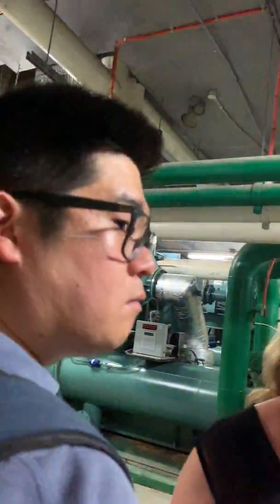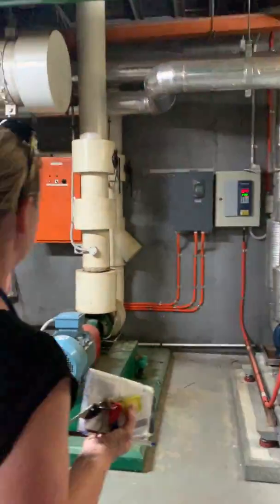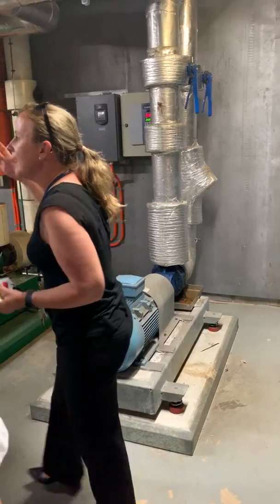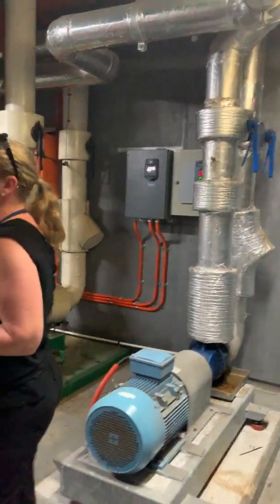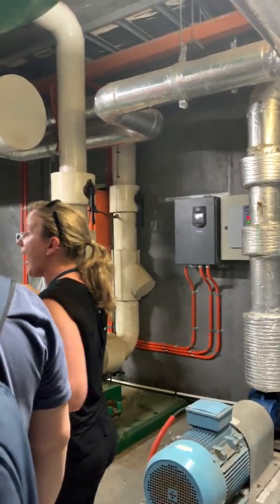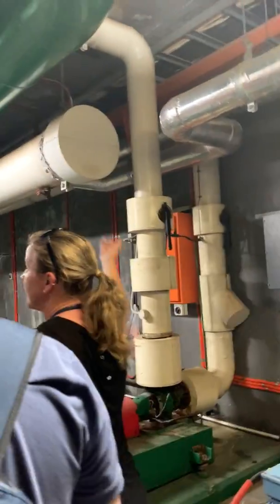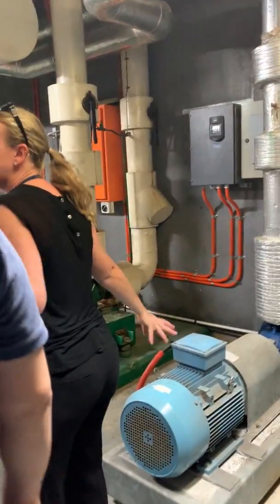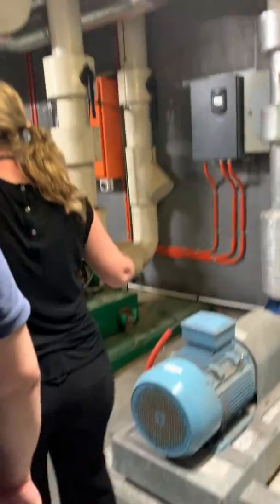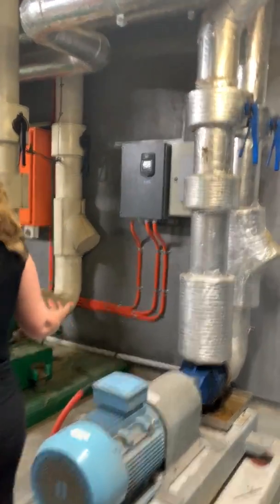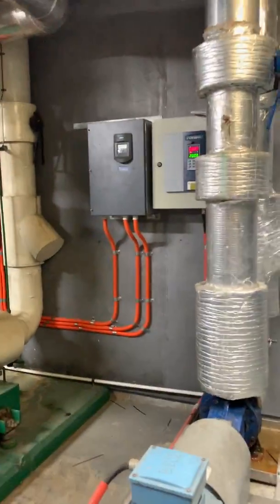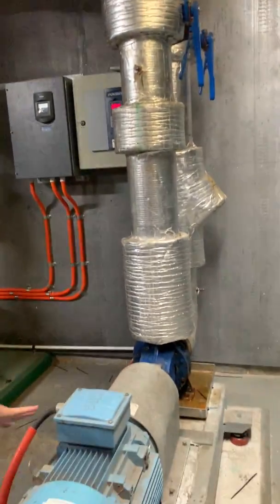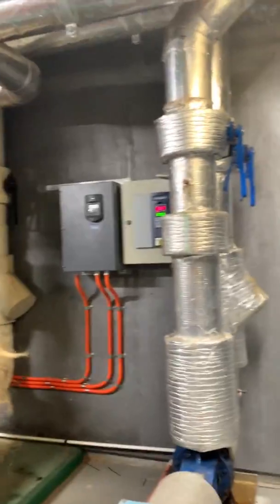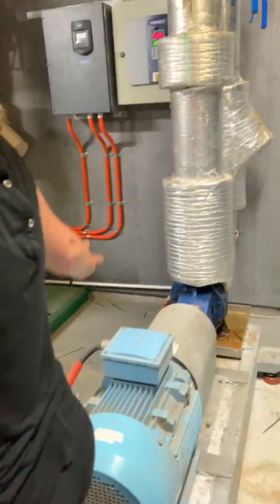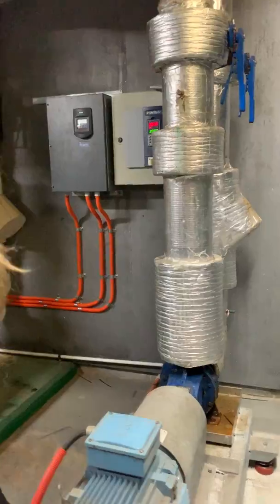The pumps that we have over here, this one is actually running. So I said before we've got a ring loop that runs all the way around campus, and the chillers that we have are feeding the chilled water into that loop. This pump is just for building 4. So this pump is taking water from that ring loop and delivering it to the air handling units for building 4. So every building on campus that's connected to this chilled water system has these pumps to draw off what it needs from the system.